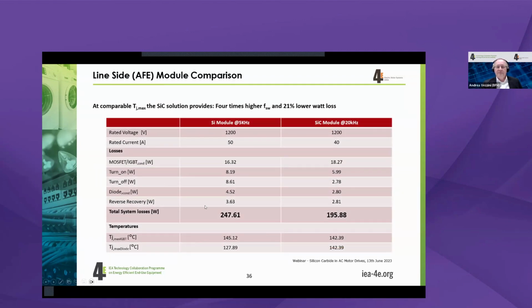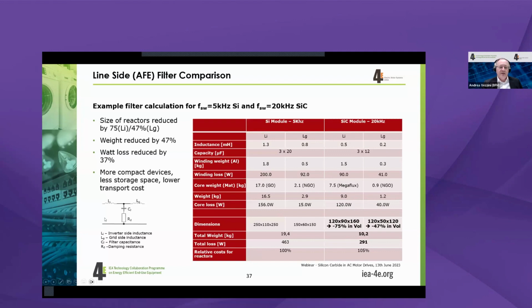But now the impact, as you can see here, will be not so much in the total system losses. So as you can see, I'm operating silicon modules at 5 kilohertz with 247 total losses from the semiconductors, whereas the silicon carbide modules, which operate 4 times higher, are at 195. So you could even go a little bit higher with the switching frequency. The big advantage now is if you look at what happens on the filter side, going from a 5 kilohertz input switching frequency to a 20 kilohertz switching frequency means that you can reduce the size of these filter reactors from more or less 75% for the inverter side, so the motor side, or 47% on the grid side.